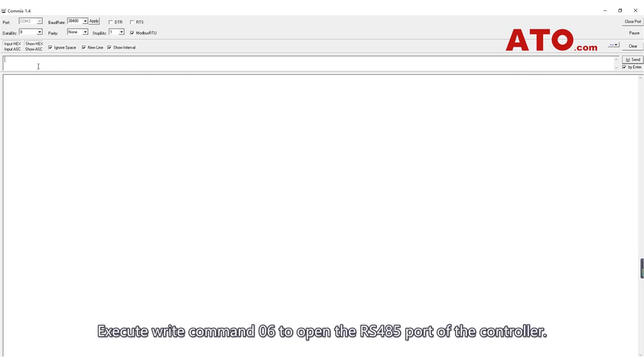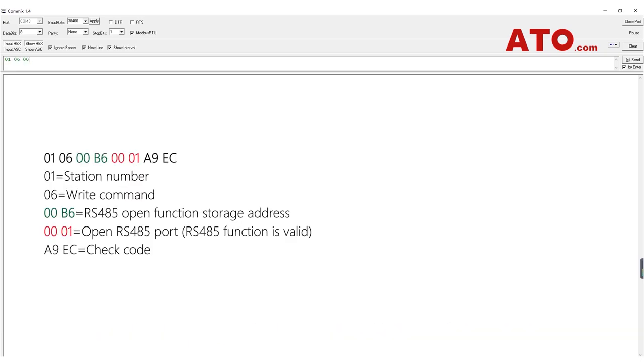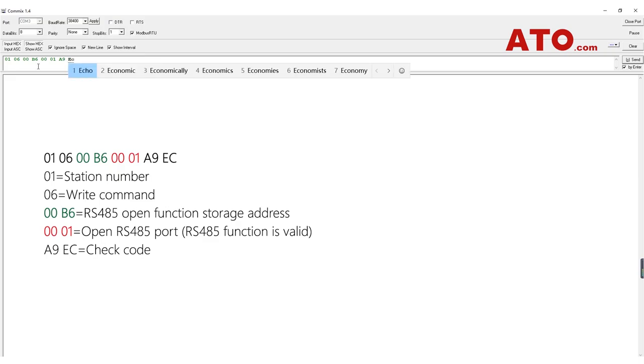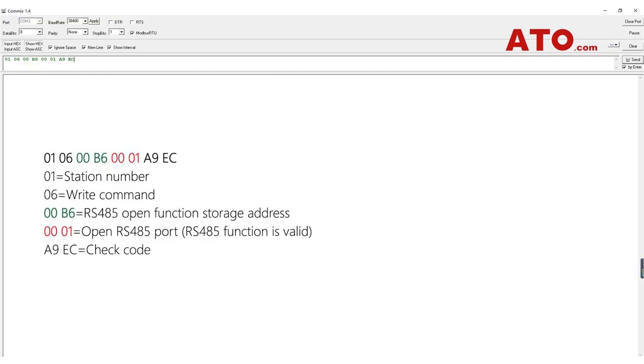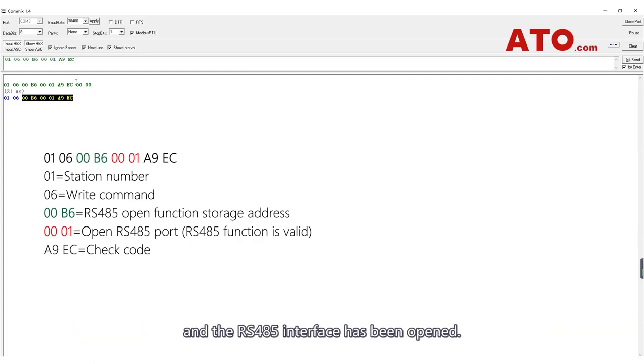Execute write command 06 to open the RS485 port of the controller. Returning the check code A9EC indicates that the command code is correct, and the RS485 interface has been opened.